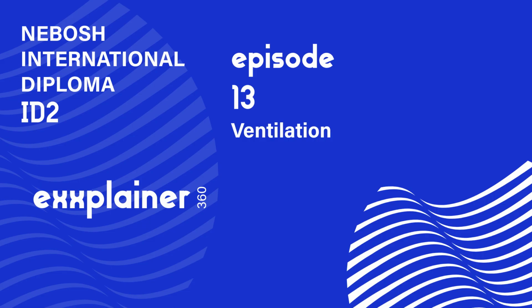Okay, so calculating the ACH is important then. Let's run through that quickly. Say a room, 5 meters by 5 meters by 3 meters high. Okay, so 5 times 5 times 3, that's 75 cubic meters of volume in the room. Right. And if the ventilation system pushes in, say, 1,000 cubic meters of fresh air every hour? Simple division. 1,000 divided by 75 gives you 13.3. So that's 13.3 air changes per hour. And you'd compare that to what the system was designed for. Exactly. If the design said you need between 10 and 15 ACH for this process, then 13.3 tells you the fan's doing its job, volume-wise at least.